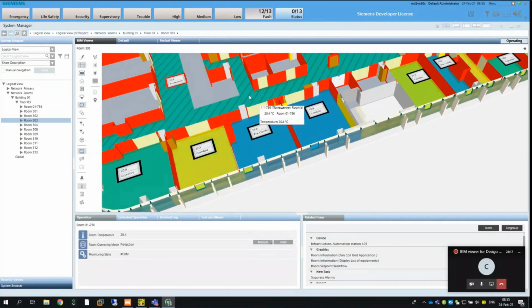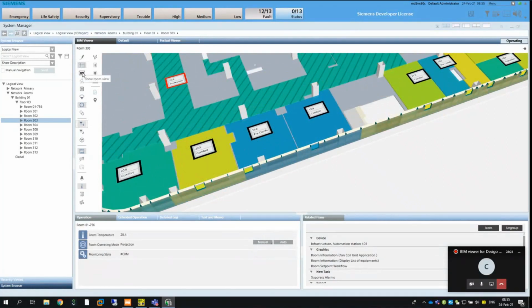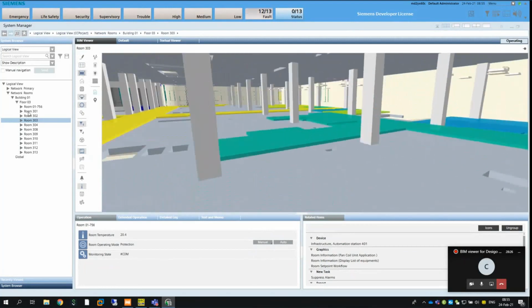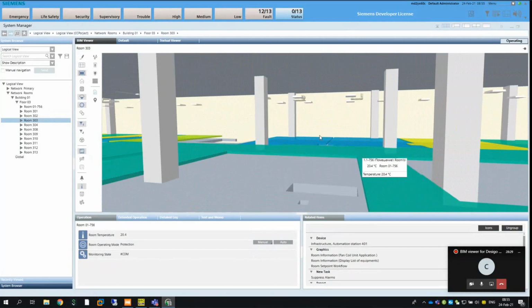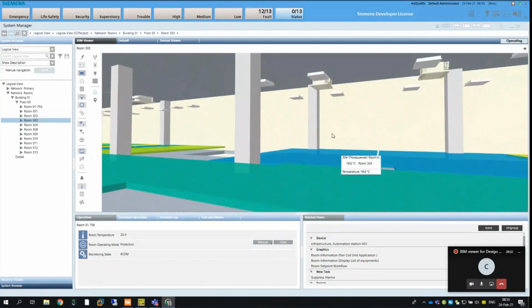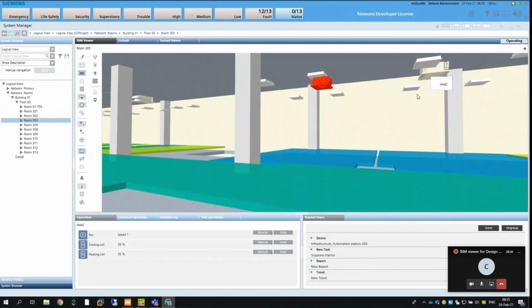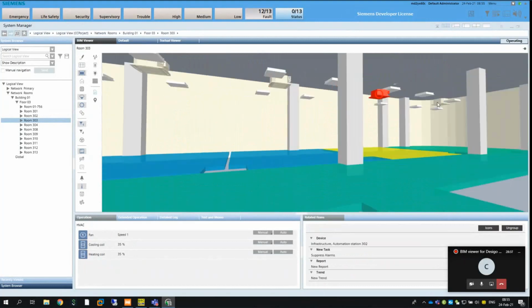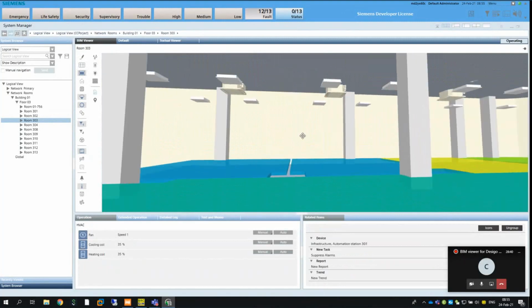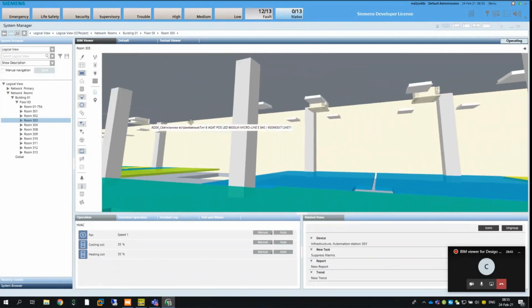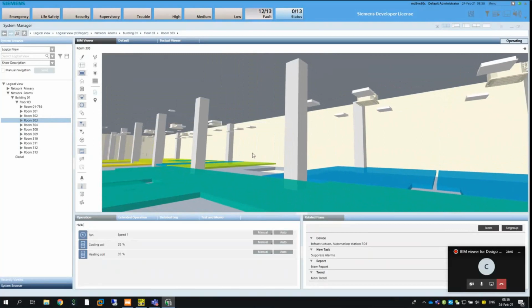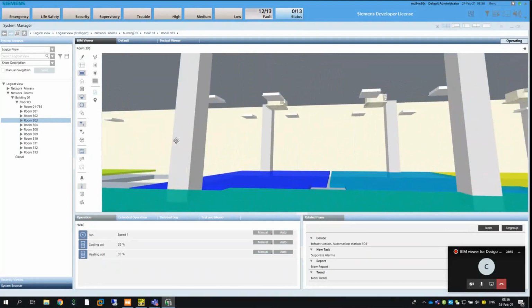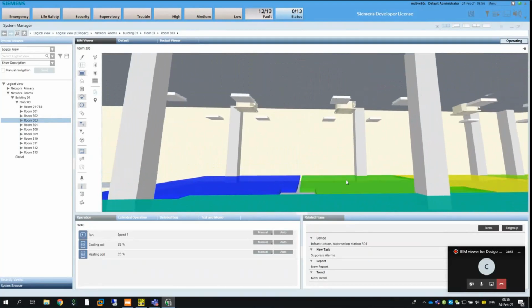Another interesting view. I will reactivate the filter, move. I can go back, and here maybe also the view with the temperature. And here we see the different HVAC equipment. You have the possibility to select here. That means if your BIM also contains the location of the different technical equipment in this type of view, and you receive an alarm, my HVAC part of this room has an issue, there is an easy way to locate the equipment and maybe to guide the person on the site.